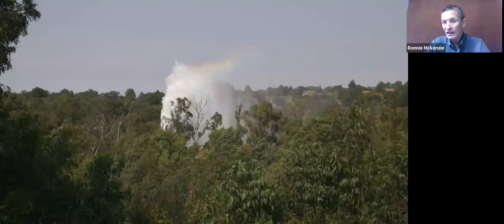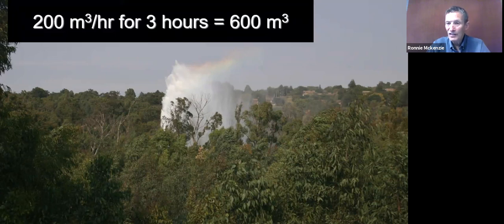Here's a very large leak. It was about a 1 meter diameter high pressure water main running at about 300 meters of pressure. One of the welds on the pipeline gave way, and you can see the water there going up to about 70 meters in height above the trees, and you can see houses in the background. This is an absolutely enormous leak. It managed to get into the newspapers and probably the TV crews would have been there. However, it was fixed again within 3 hours.